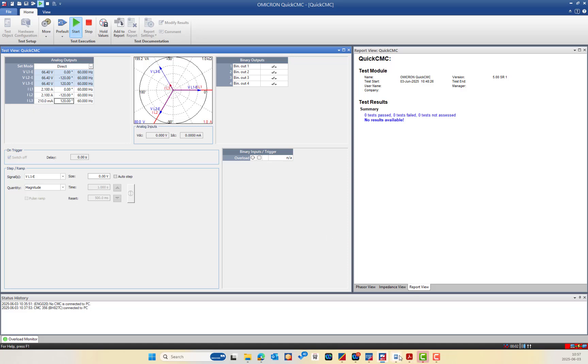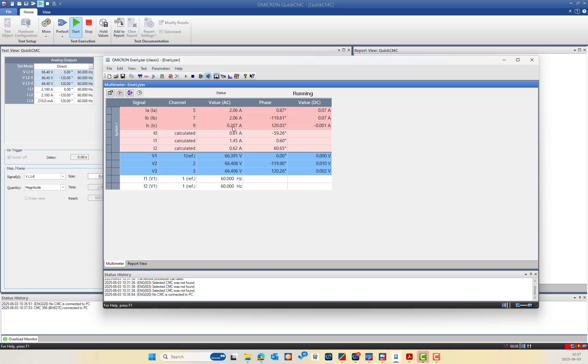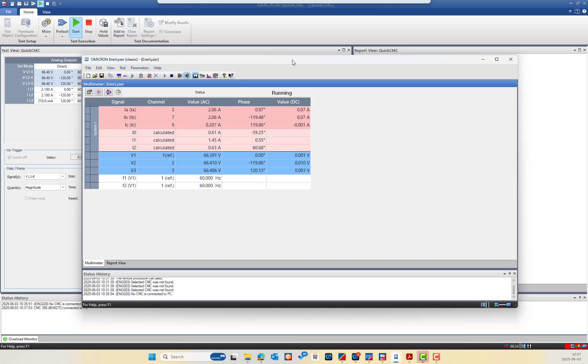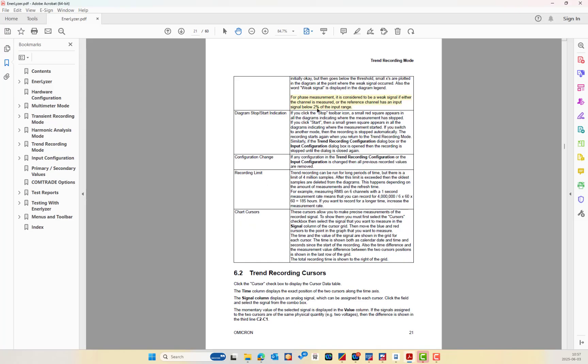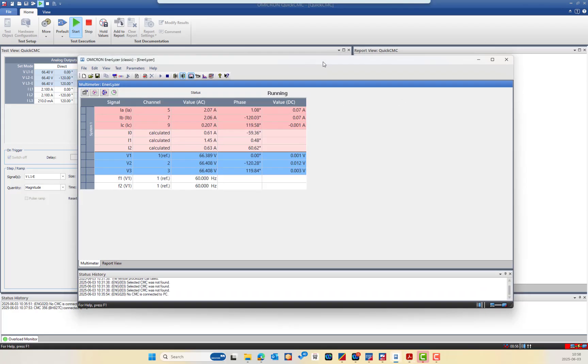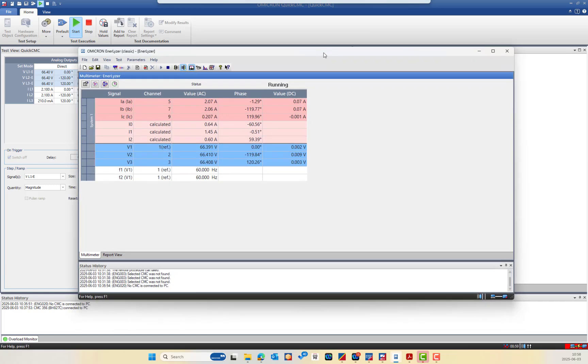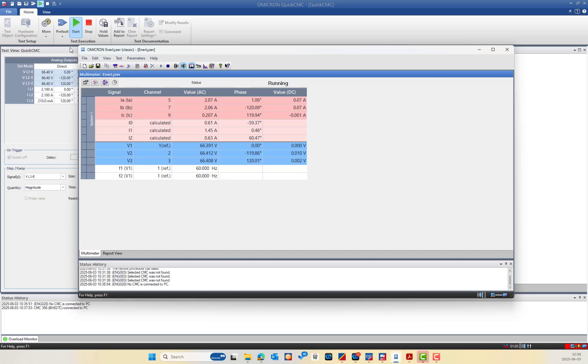At 210 mA, the IC phase angle appears correctly. The rule is: if you exceed 2% of the nominal range, the phase angle measurement is given and the weak signal resets. You can verify this in the Analyzer manual, page 21: it is considered a weak signal if either the measured channel or the reference channel has an input signal below 2% of the input range. I hope everything is clear, and please feel free to reach out or message in the WhatsApp group.